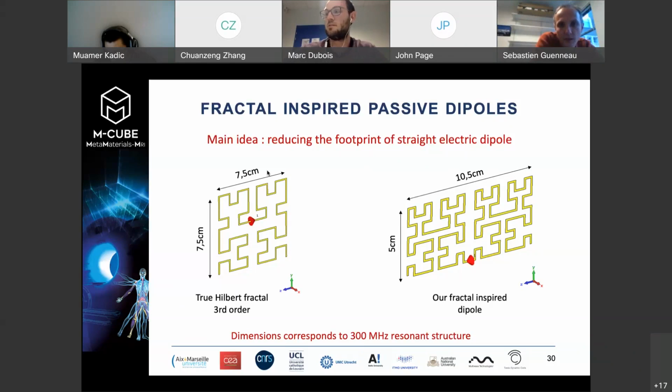So in terms of heat, you want to manage the SAR. You don't want SAR, which is related to the electric field, to get absorbed in the tissue and cause a temperature rise. Today we use this figure of merit, SAR, as one way to calculate a threshold at which it's dangerous or not dangerous. The threshold is, for example, if the entire body increases by 1 degree. But you have to think that the blood circulates, so it will diffuse the heat everywhere in the body.